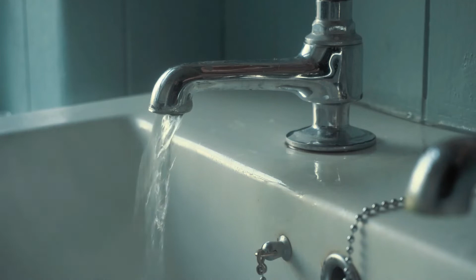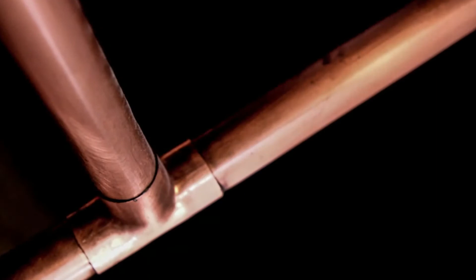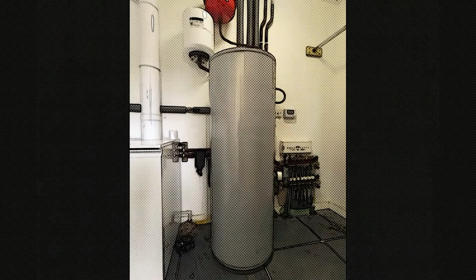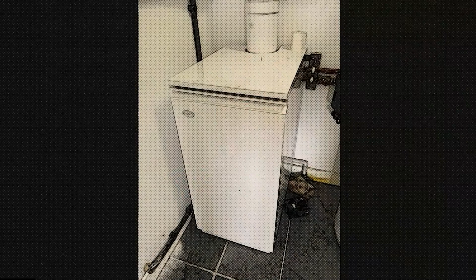Here's an example: hot water use. Think about what happens when you turn a tap to wash your hands. You might use half a litre of hot water, but if the boiler is 15 metres away, and the pipe is 15 millimetres in diameter, a further 2.5 litres would have been heated and left sitting in the pipe run after you turn the tap off. This indicates a possible 5-fold error in the energy estimation. Then maybe the water has come from a hot water tank, which will have its own losses. Finally, the water might have been heated by a boiler, which will not be 100% efficient. In total, this can create a 10-fold error in the estimation of energy used to supply the hot water.